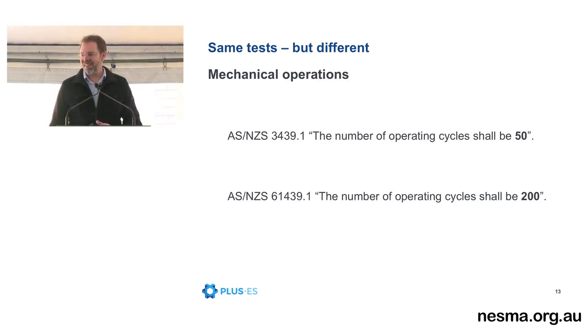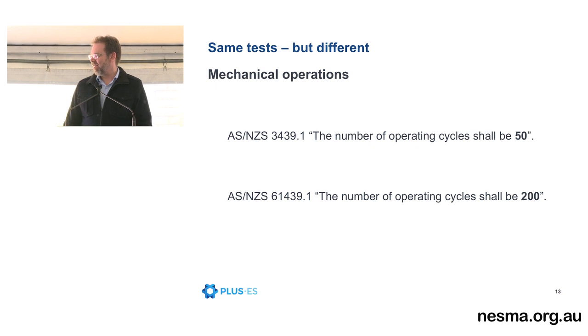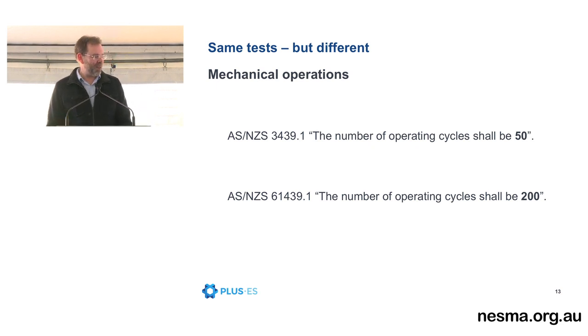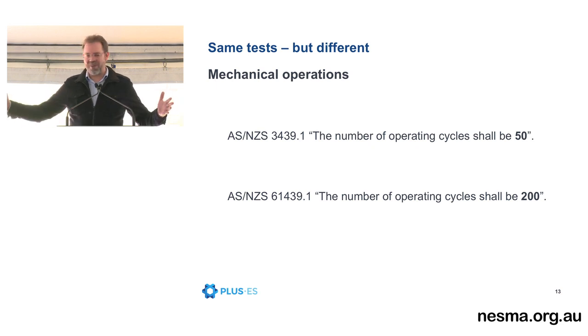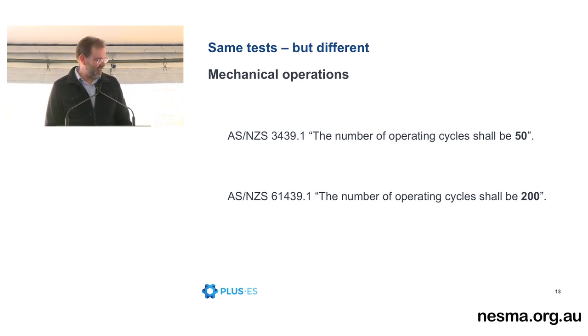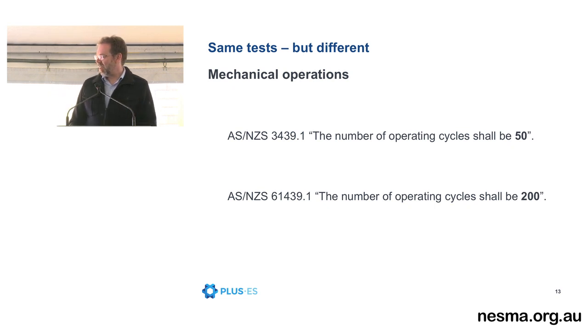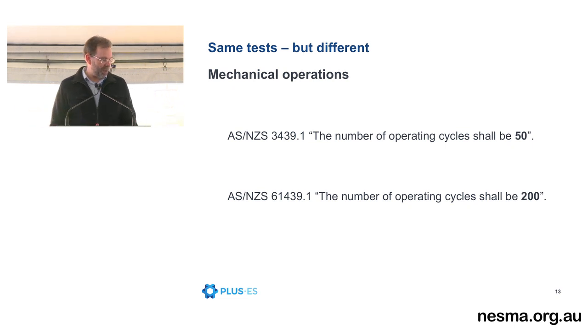Mechanical operations. I find this one, I shouldn't laugh at this, but AS3439 had 50 mechanical operations. Now we have to do 200. And when you're doing a double pole 6300 amp withdrawable unit, it's about that wide. 200 operations is actually a lot of physical labour. What's even more interesting is that the circuit breaker standard, the 947 series, requires for a withdrawable breaker in its own cradle to do 100 operations. So there we go. You put it in an assembly, all of a sudden you have to double the number of operations.